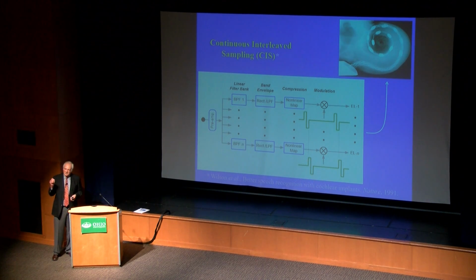The range between just hearing something and a percept that's close to intolerably loud is very narrow in electrical stimulation of the auditory nerve, on the order of 10 dB. Whereas in normal hearing, we have a range that exceeds 90 dB. So somehow this wide range has to be narrowed down to a very narrow dynamic range. Otherwise, the person using the cochlear implant wouldn't perceive much of the normal range of hearing. And that's the function of this nonlinear map, which greatly compresses the dynamic range of variations coming out of this energy detector.